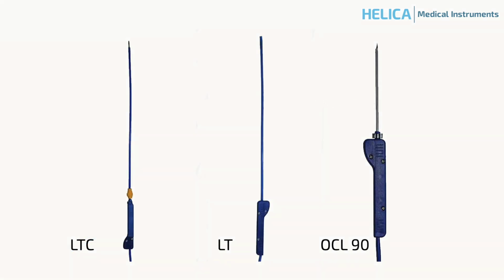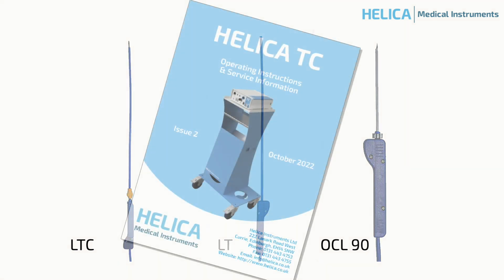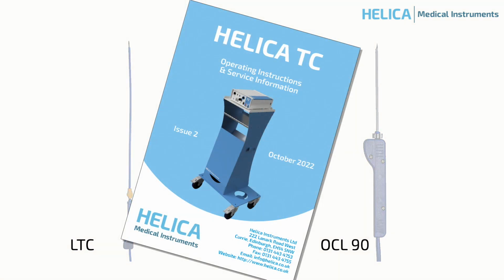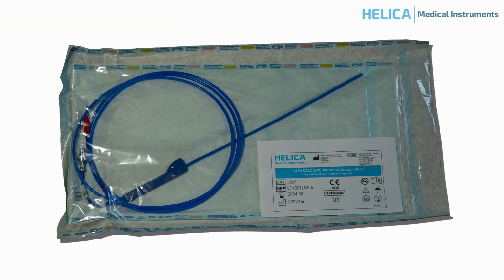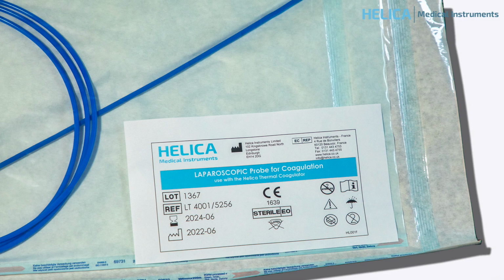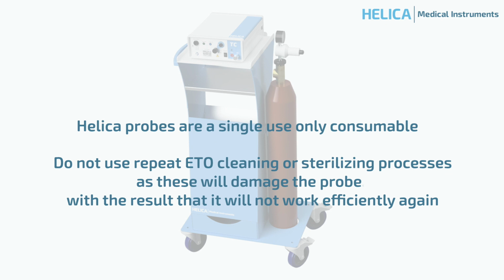There are a variety of different lengths and types of probes to suit specific applications. Please refer to the Helica literature to identify which is most suitable for your requirements. Each probe is supplied as a single unit within a double-wrapped sterile pack with an appropriate code for ease of identification before use or when reordering. The probes are a single-use only consumable. Do not use repeat ETO cleaning or sterilizing processes, as these will damage the probe, with the result that it won't work efficiently again.